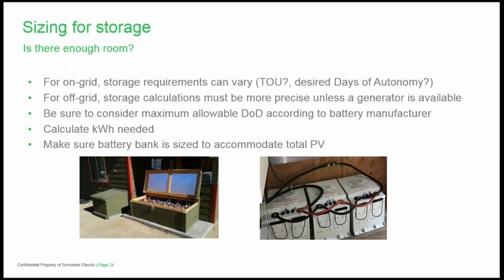Make sure the battery bank is sized to accommodate the total PV. That's important because if you're AC coupling, say the customer goes on vacation and there's an outage, then virtually all of that PV power is going to be pushed into the battery. So that battery must be sized to safely accept that total amount of PV. Likewise, if you're DC coupling, some people even choose to AC couple and DC couple. So you need to consider all of your charging sources and make sure that that amount doesn't exceed the manufacturer's recommendation for maximum charge rate for their battery.